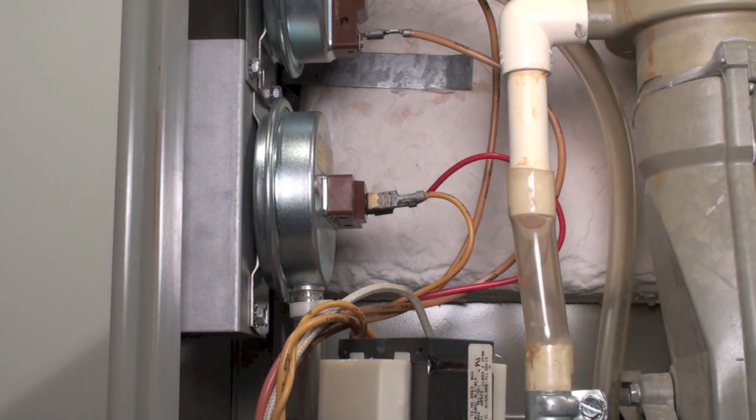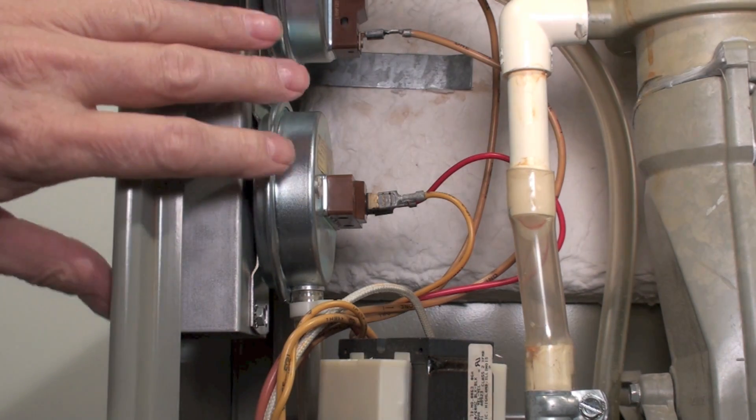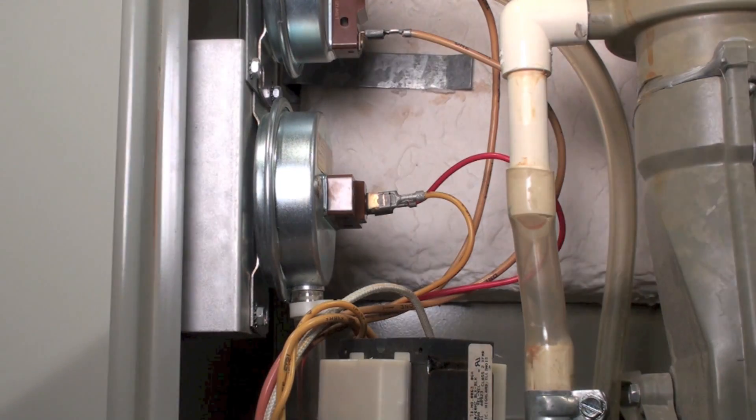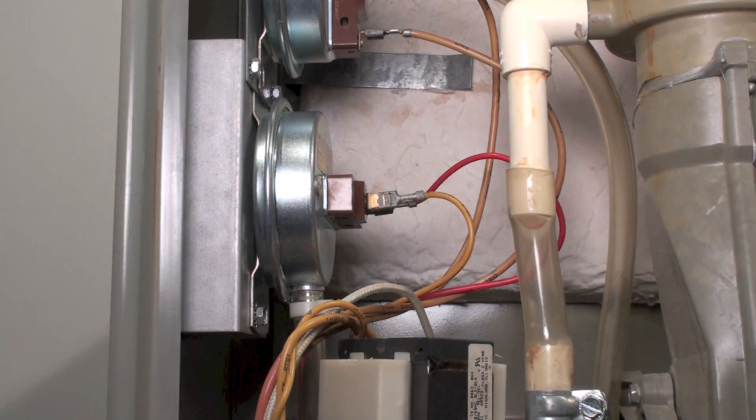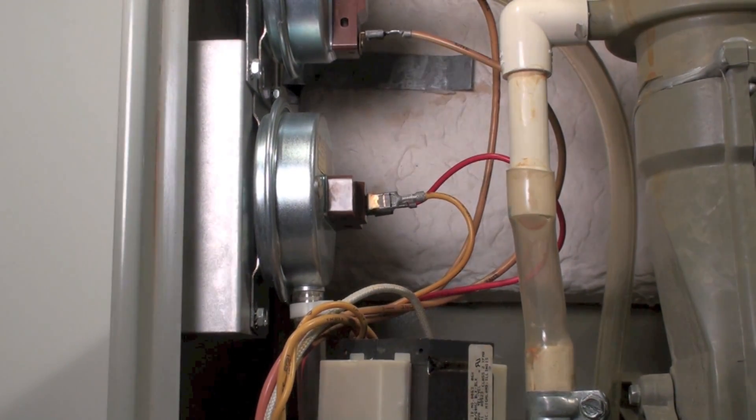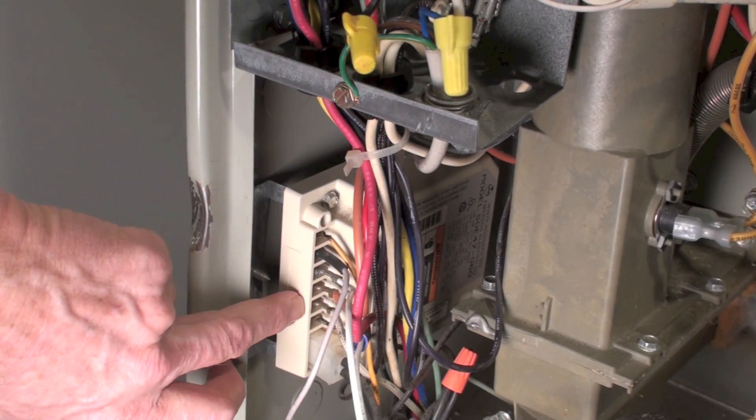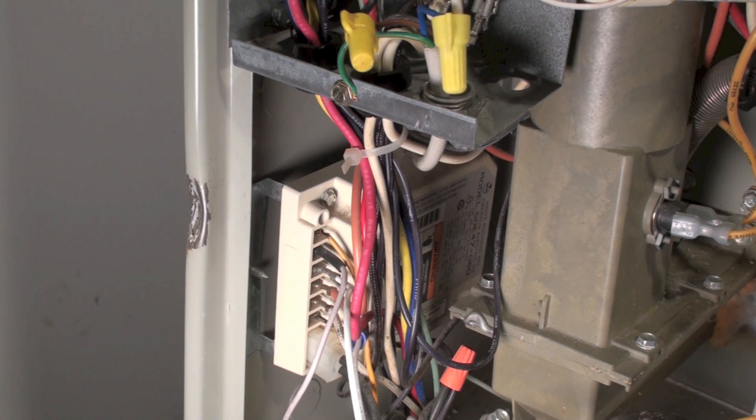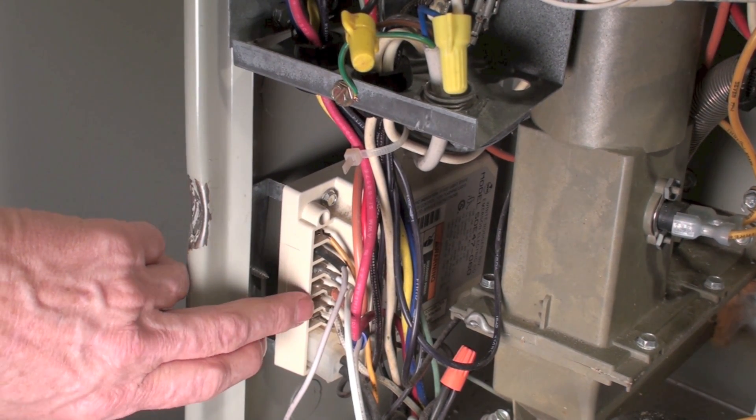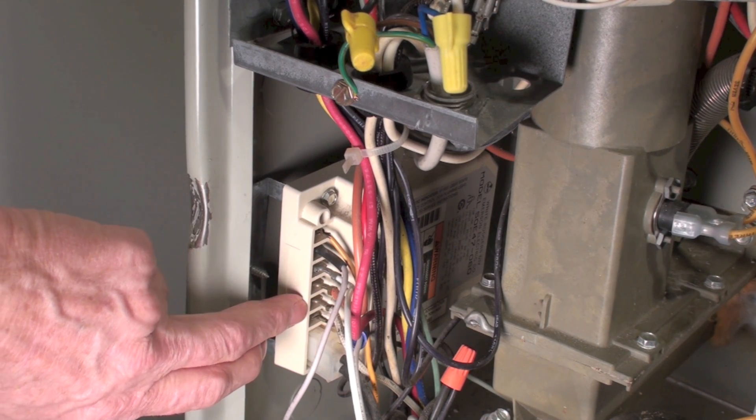Once that pressure switch is closed, it gets power and begins the sequence. This starts the timing for the hot surface igniter. The hot surface igniter warms, and then you get a trial for ignition.